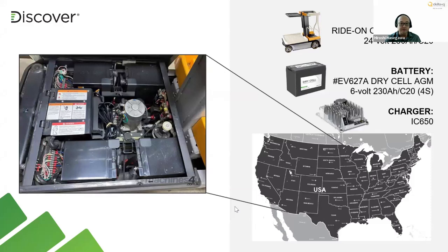Adding on to that, as I mentioned earlier talking about the different technologies, the disadvantage with flooded battery is the need to top up with water, but it's also more forgiving in that sense because you can somewhat reverse the effects. If you overcharge or over discharge, you can add water back in and be up and running again. Is it going to be back to 100% health? No, because it's damaged, but it will still work and do the job relatively well.